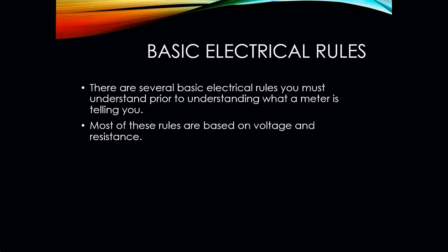So there are some basic rules that we need to follow before we even get to understand what the meter is doing. We need to understand basic electrical and the rules that apply to it. Most of these rules are based on voltage and resistance. Voltage and resistance in any sort of electrical troubleshooting are the two most important readings that a technician can take. Without taking a voltage reading, we don't even know if there's power applied to the system. Without taking a resistance reading, we cannot tell whether or not a load, or some power-consuming device in that circuit, is actually still working.